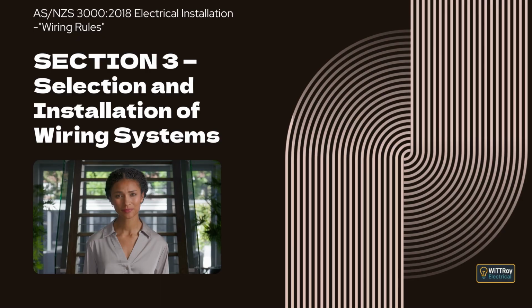Clause 3.11.5, Spacing from other underground services. This clause explains that underground wiring systems must be separated from other underground services by at least 100 mm. They must also maintain separation from gas, water, and telecommunications services in accordance with the required spacing rules. Exceptions are allowed where multiple services are installed in a common trench, provided each service is in a separate enclosure and clearly identified. Clause 3.12, Aerial wiring systems.